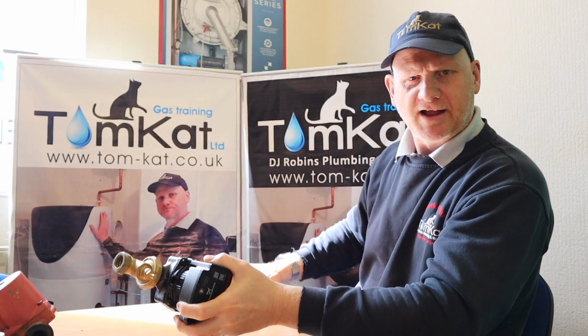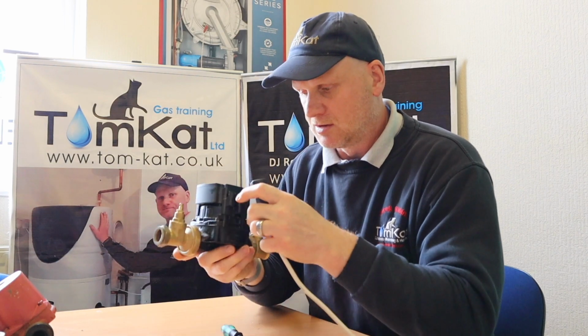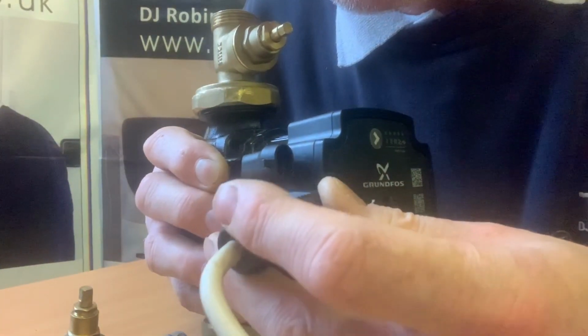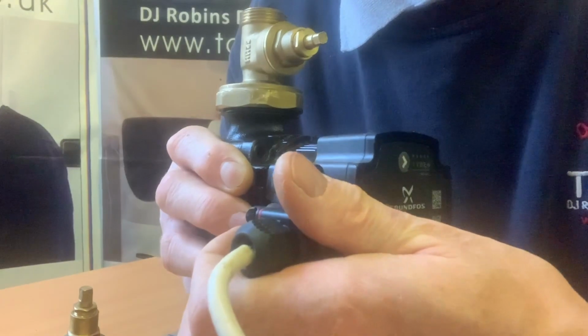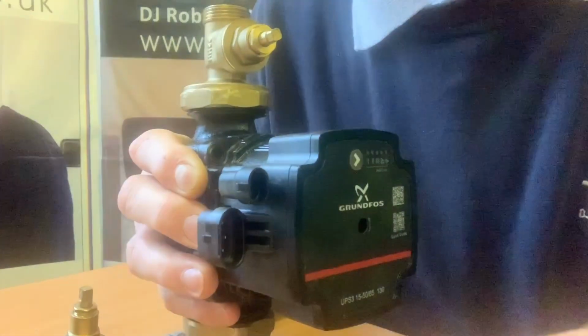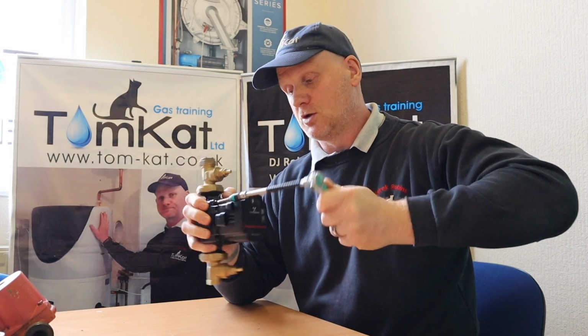Now the first big difference we see is they've changed the colour. Don't know why they've done that, but anyway, they've changed the colour. Second big change is how you wire it up. There's a plug now. It's over here, hang on. We've now got this external plug that clips on. So you're wiring that up, you're not actually going into the pump head now. Now it's still got the same 4 screws, and we've still got the cutouts on the pump head, so we can still undo the pump.